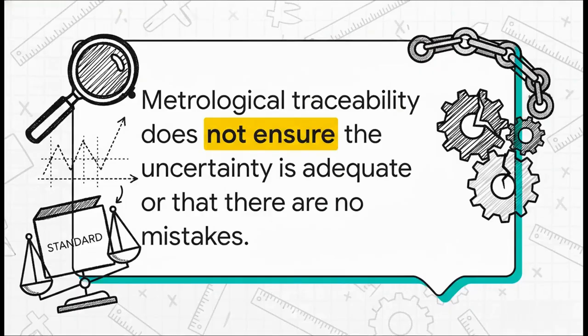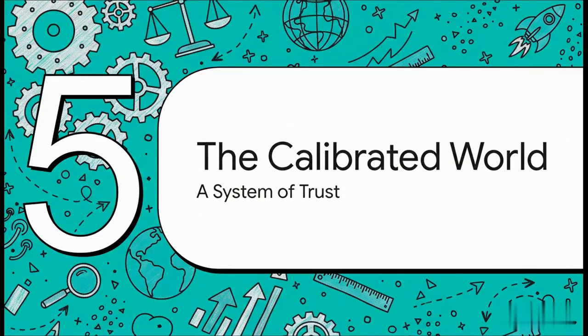And this quote from NIST really just ties a perfect bow on it. Having a traceable measurement gives you confidence, for sure, but it doesn't magically make uncertainty disappear, and it certainly doesn't mean you can't make a mistake. All traceability does is prove your measurement is linked to the official standard. The uncertainty statement is what tells you just how good that measurement actually is. So let's zoom out and put this all together. You've got calibration, this active comparison, you've got traceability, this chain of trust, and you've got uncertainty, this honest admission of doubt. The combination of all three creates this incredible global system that allows us to build and trade and innovate with a huge amount of confidence.